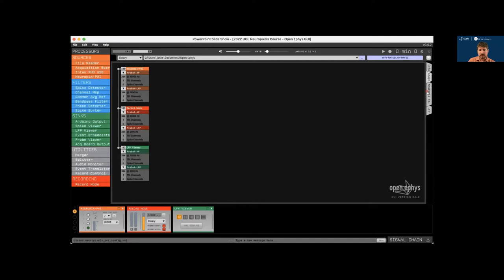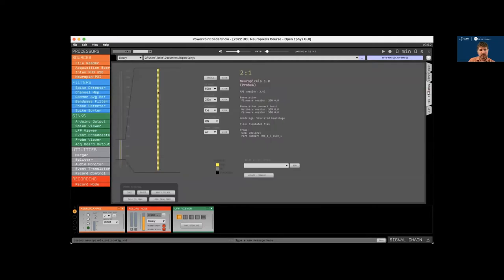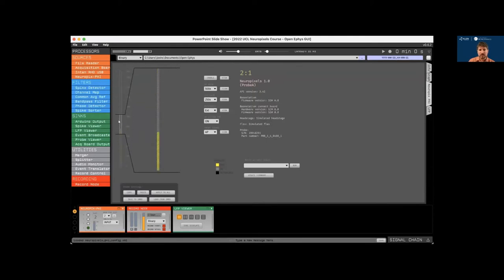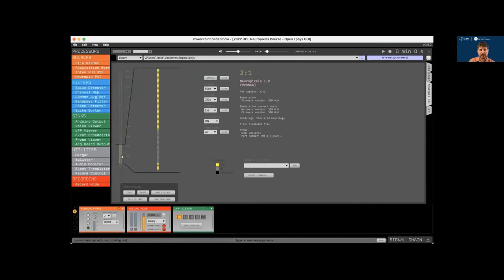Now we'll switch to the Neuropixels settings interface. You can see on the left-hand side, we have a visualization of the probe that can be used to scroll through all of the 960 available electrodes, see which ones are active. If we select a subset and hit enable, it will activate the selected electrodes while deactivating the other electrodes near the tip that are connected to the same set of channels.